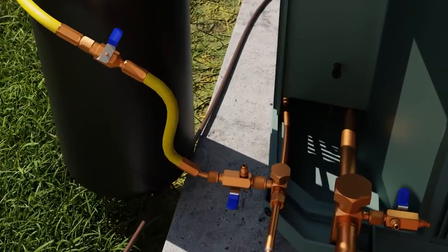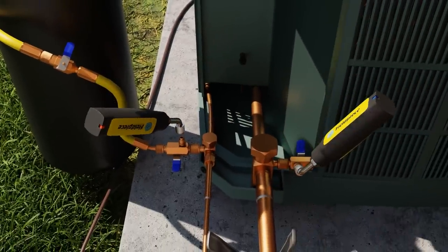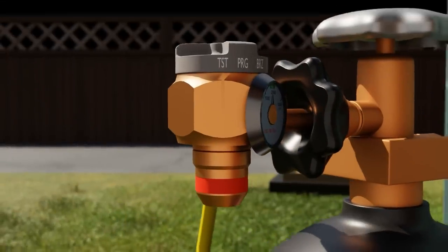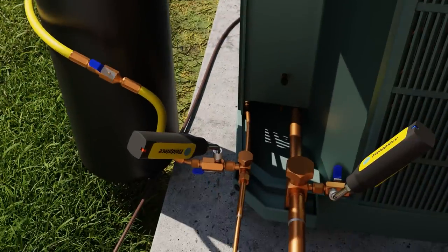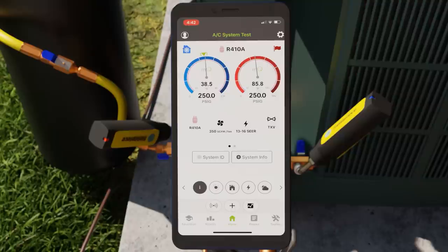We know we pressure test with nitrogen. The question sometimes comes up: what do we pressure test to? The answer is the highest safe pressure. When you pressurize a system by putting nitrogen in the high side and watch the low side go up, at some point the high side keeps going up and the low side pegs out.